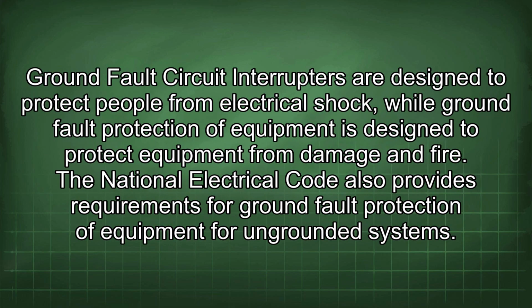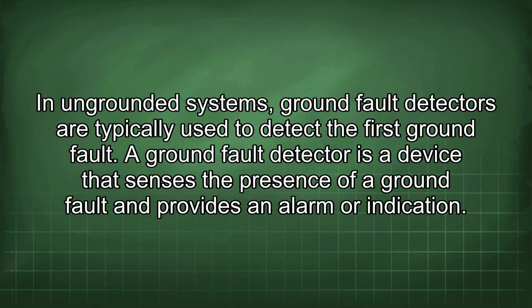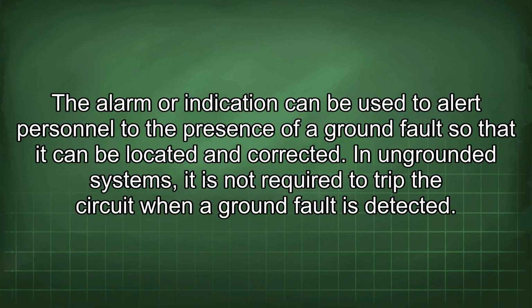Ground fault circuit interrupters are designed to protect people from electrical shock, while ground fault protection of equipment is designed to protect equipment from damage and fire. The National Electrical Code also provides requirements for ground fault protection of equipment for ungrounded systems. In ungrounded systems, ground fault detectors are typically used to detect the first ground fault. A ground fault detector is a device that senses the presence of a ground fault and provides an alarm or indication. The alarm or indication can be used to alert personnel to the presence of a ground fault so that it can be located and corrected.